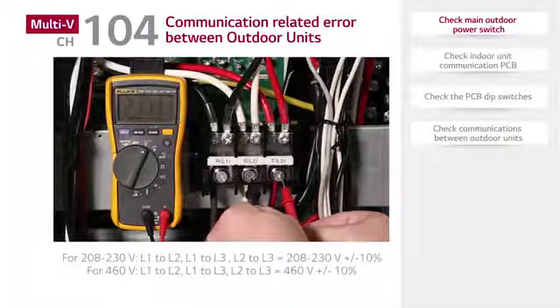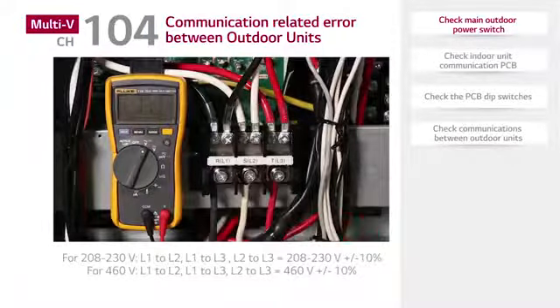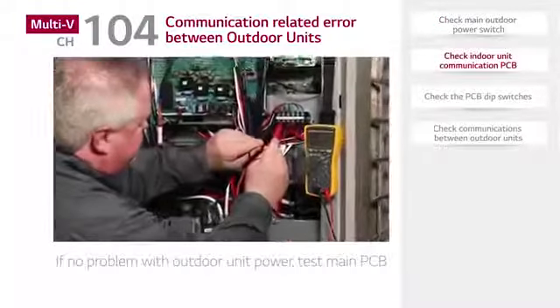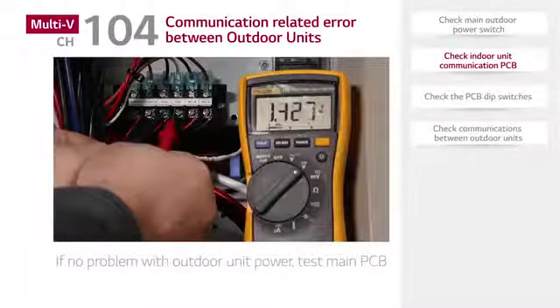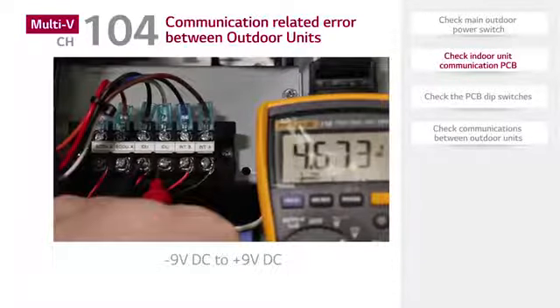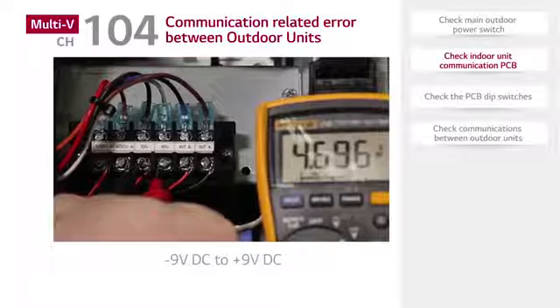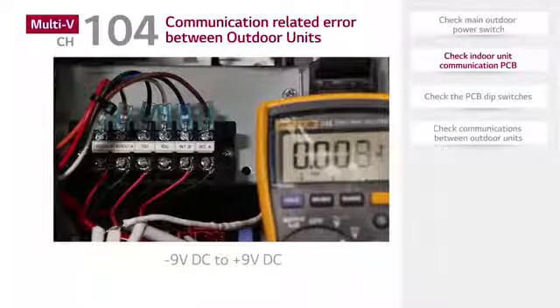And for 460 volt equipment, L1 to L2, L1 to L3, and L2 to L3 readings should be 460 volts plus or minus 10%. If there is no problem with the outdoor unit power, test the main PCB. First, check the communication signal to the indoor units. The normal voltage value for the communication signal should vary from -9 volts DC to +9 volts DC.